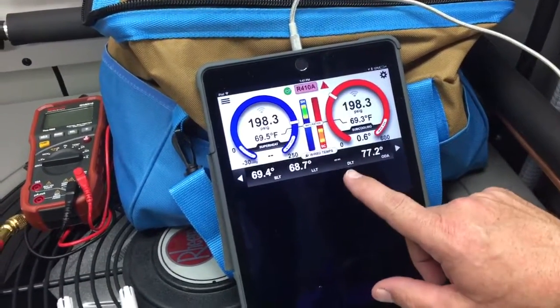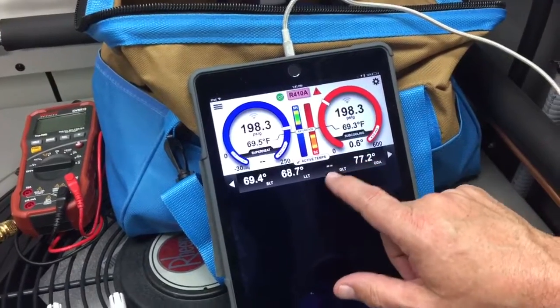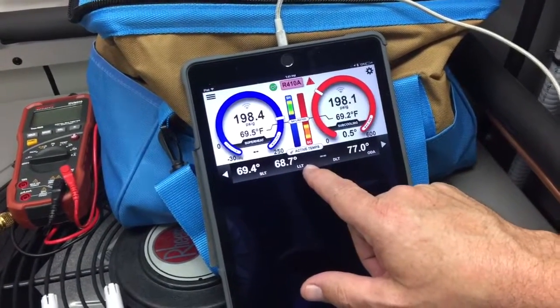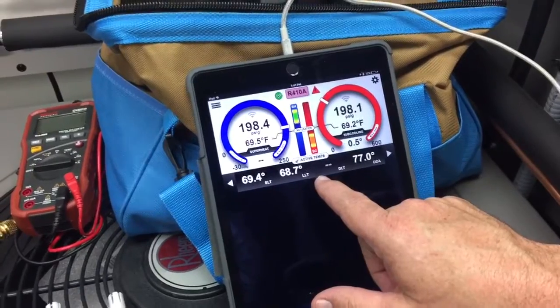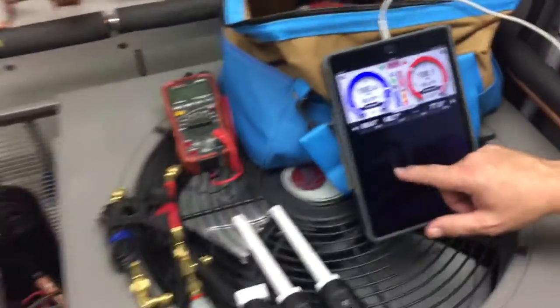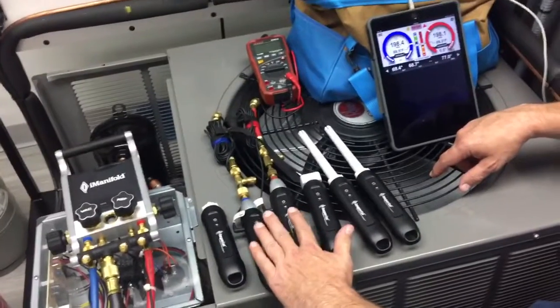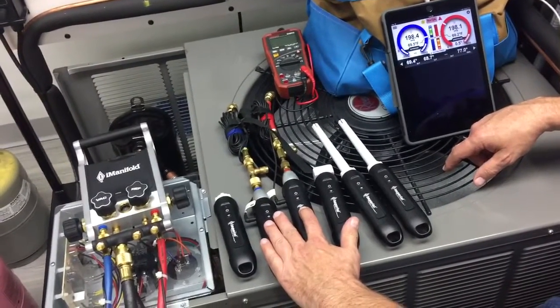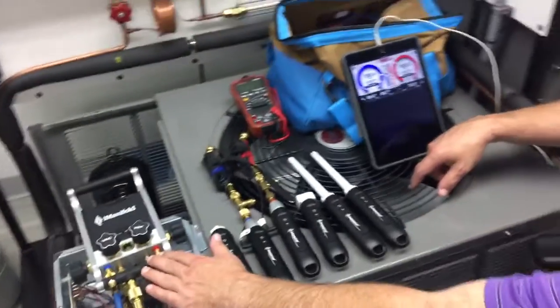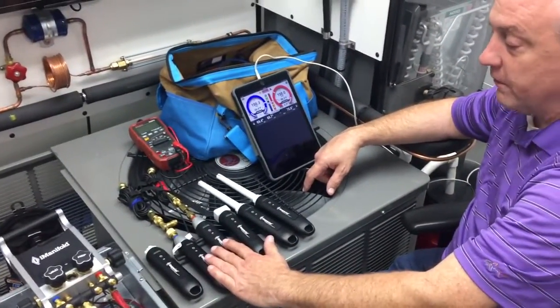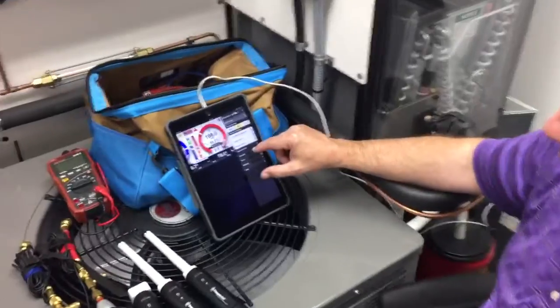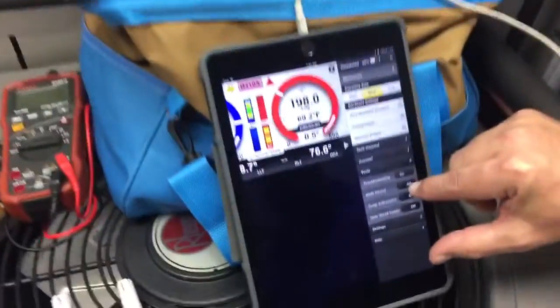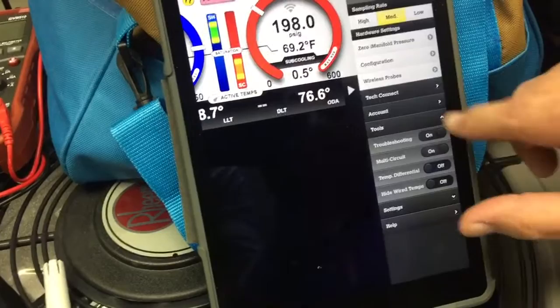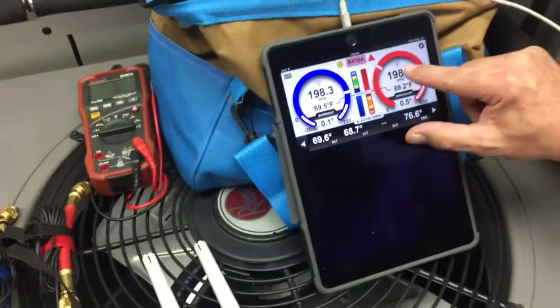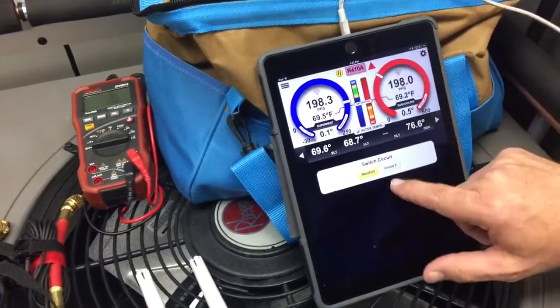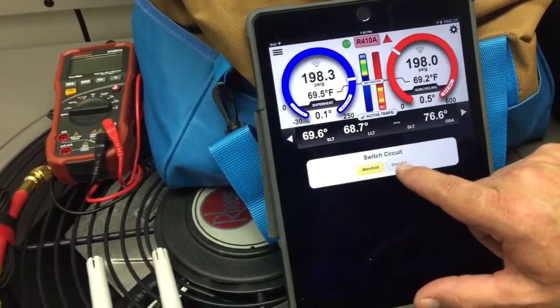There is a difference between wired temps and active temps, and if I scroll back here for a minute, active temps are the active temperatures for the circuit I'm working on. Remember here I have these high and low pressure probes, so I could use these for a second circuit, like if I had a two-stage machine where I use the iManifold for circuit 1 and an additional high and low pressure probe for circuit 2. If I go into the tools here and I turn on multi-circuit mode, you see that's turned on now, and I just slip back here and touch either one of the wireless symbols at the top, it'll allow me to switch circuits from the iManifold to circuit 2.